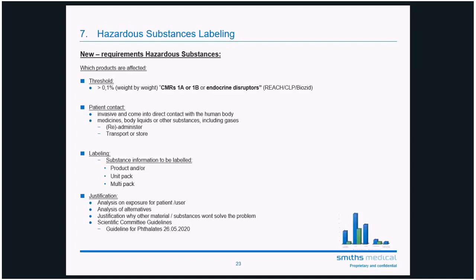And keep in mind that the criteria listed in that section, I think it's 10.4.5 of Annex 1, are quite tricky. So you have to take into account in your justification the analysis of how the patient or the user is exposed. You have to analyze if there are alternatives available. And then, in a nutshell, you have to justify why the other materials, if there are alternatives, won't solve your problem. So also consider scientific committee guidelines, such as guidelines that will be coming forth, delayed, such as DEHP.